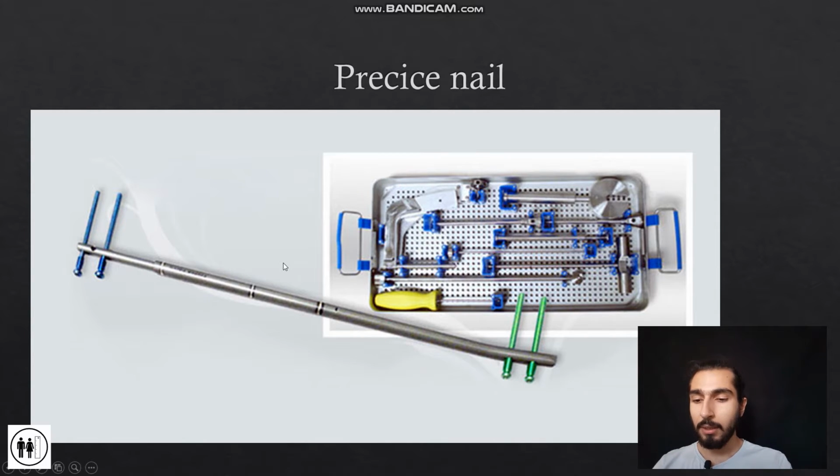And Precice uses a little different mechanism and lacks that induction coil attachment, I mean the part that sticks out. So these nails allow distraction of the bone in both ways.